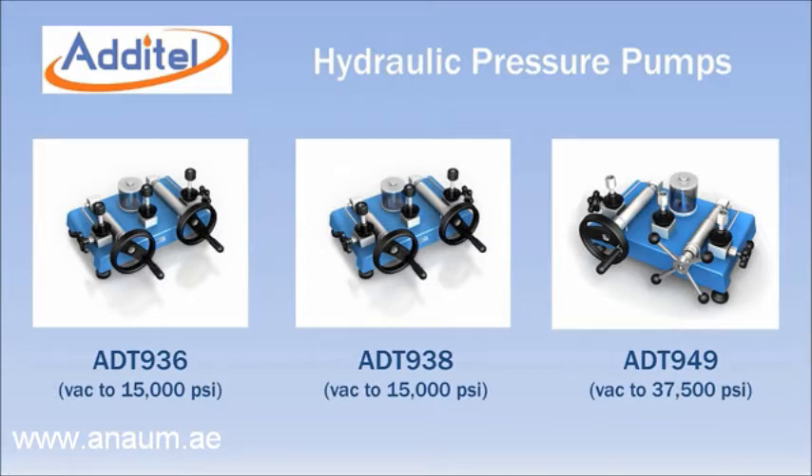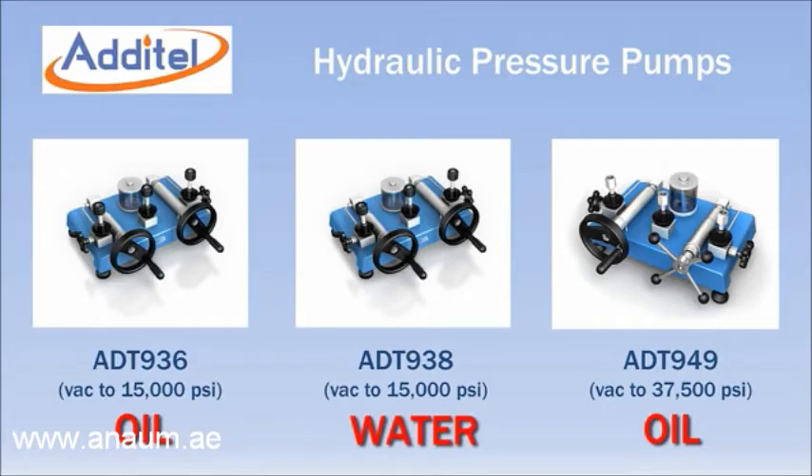The Additel ADT 936, 938, and 949 are benchtop hydraulic pressure pumps with maximum ranges of 15,000 PSI for the ADT 936 and 938, and 37,500 PSI for the ADT 949. All three models also generate vacuum. The 936 and 949 are designed for oil service, while the 938 is specifically designed for oil-free calibrations using water as the media.